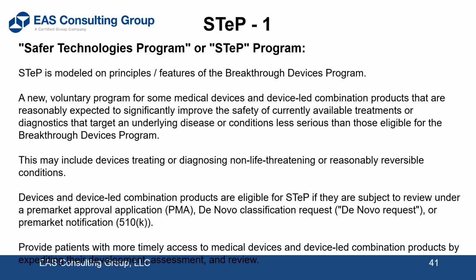Basically, this is a voluntary program again, but sometimes the FDA may recommend you take this approach when you submit. But that's kind of late. But if they become aware of something, they may recommend that approach. You should be aware that if you have a product that is safer, it doesn't raise any major issues in safety and effectiveness, but you can actually show that you reduce risk to the patient, reduce use error, reduce follow-up procedures, and things like that, your product may be a candidate for the STEP program.